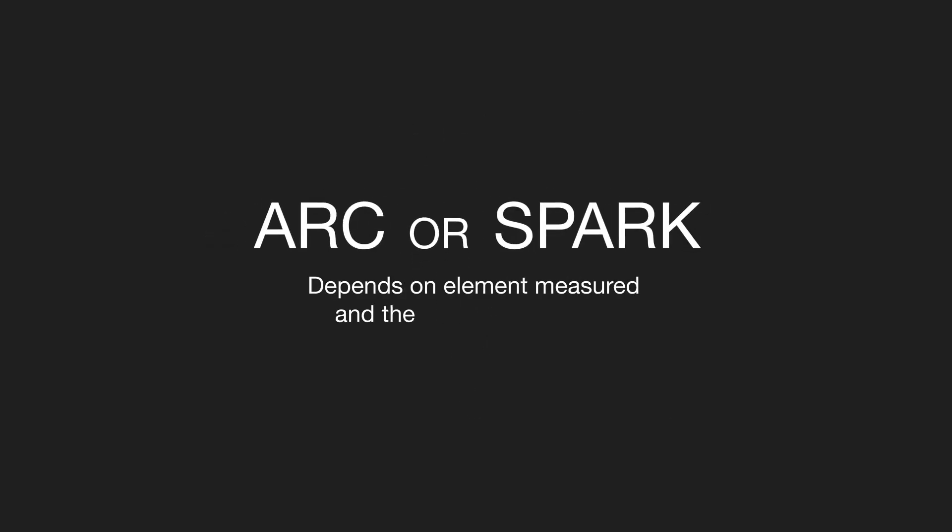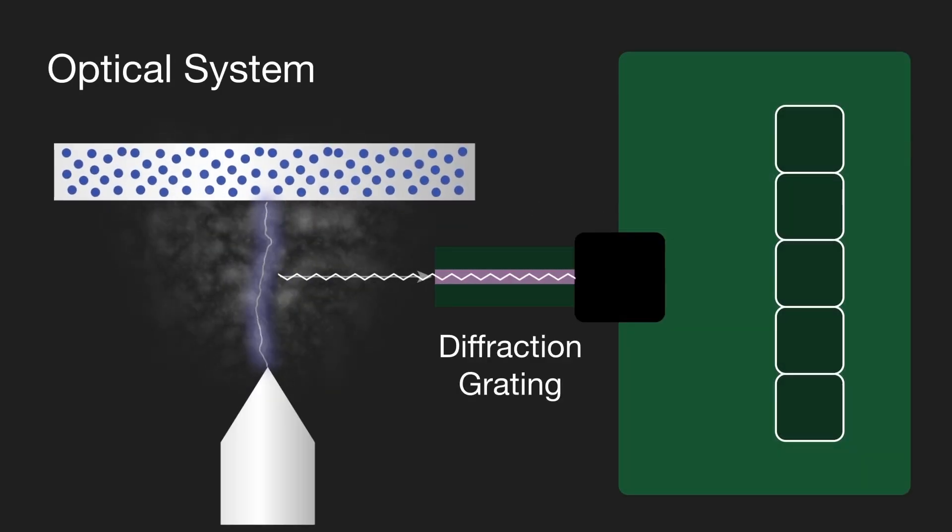These two modes of operation are used depending on the element measured and the accuracy required. The second component is an optical system. The multiple optical emission lines from the vaporized sample, known as a plasma, pass into the spectrometer.